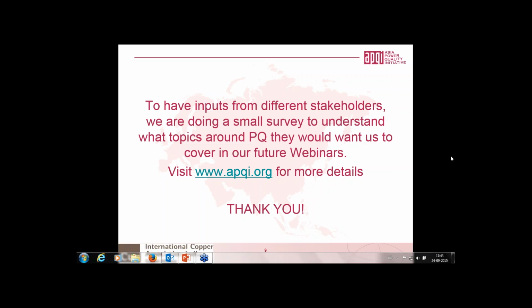Before I respond, I was just adding onto the outage period: there are power quality indices for supply utilities named SAIFI and SAIDI, which give comfort to the consumer in terms of interruptions and their frequency. To the question on 0.2 and 0.2s, the basic difference is in the CT accuracy. It is for lower loads, and the internal design makes a composite solution of 0.2s. So it's a special class for the meter.